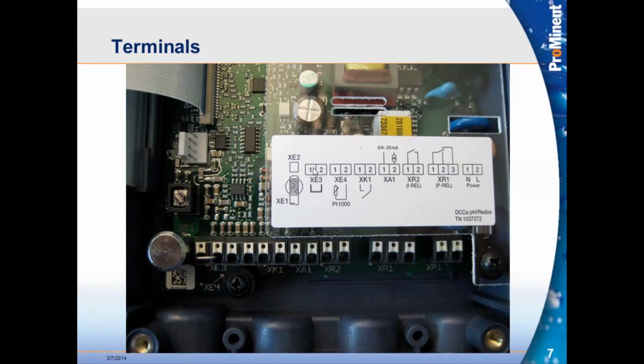To the right of that, we have our jumper. We'll talk about that. We would replace that jumper if we have a reference signal. To the right of that, our PT1000 temperature sensor. We have our digital input. Remember, if we're controlling with this unit, we need to know if our sample line has stopped. The premise there is if the sample line is stopped, we're thinking that that comes off of the process. Therefore, we're thinking that the process is stopped, and we don't want to continue injecting a chemical into a process line that in thought is stopped. So be cautious with that. Always include that flow switch on the DGMA or get that signal from another point in the process.